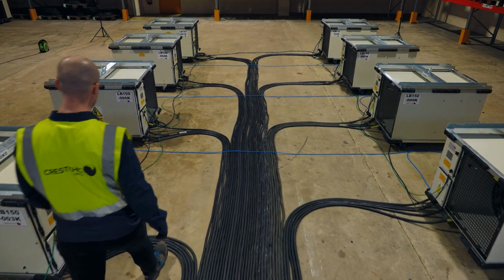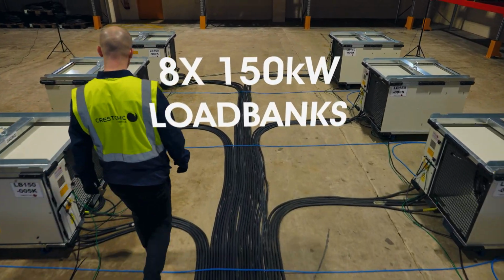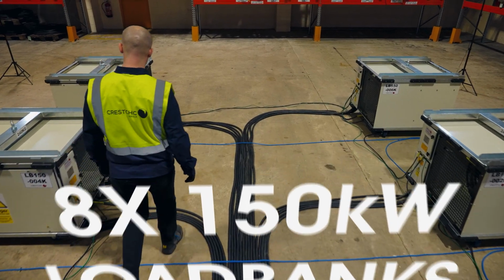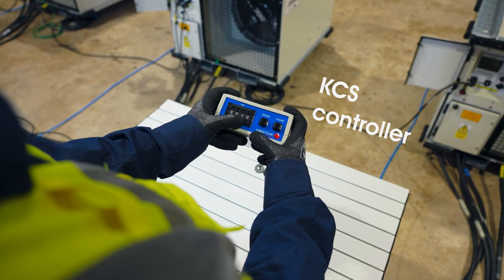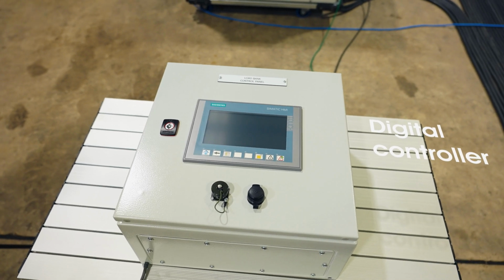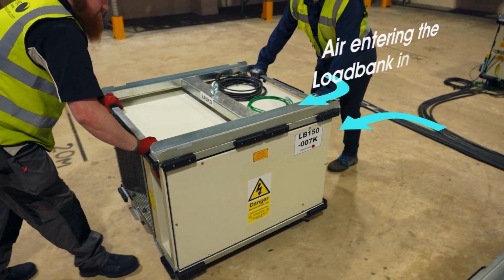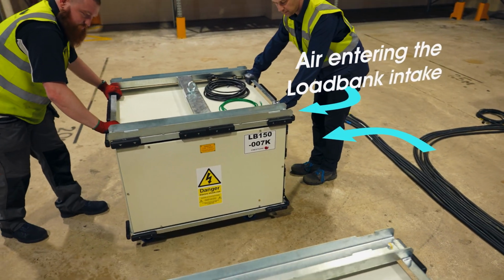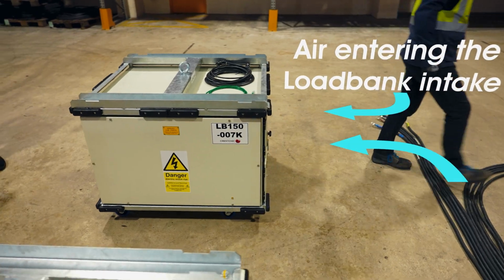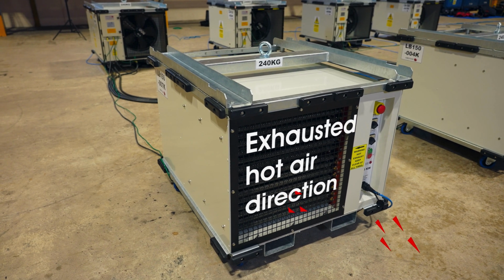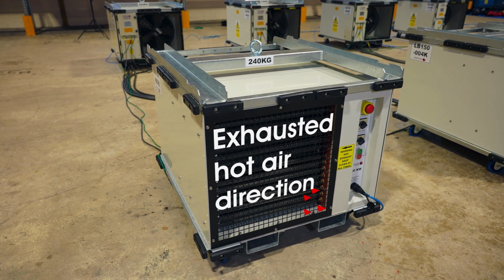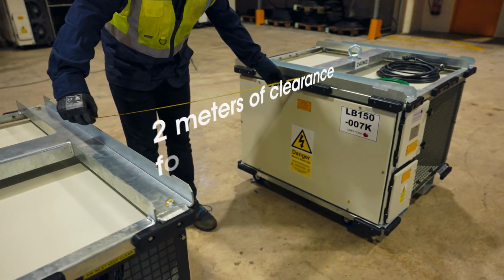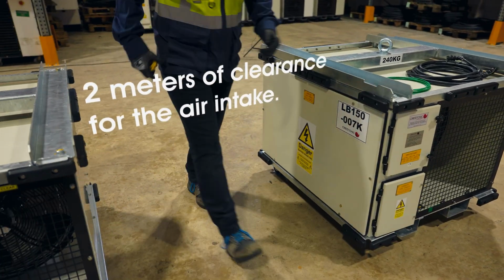In this short video, we are going to show you a typical test using 8 times 150 kilowatt load banks with both our KCS controller and our digital controller. The load bank should be placed so that there is adequate air entering the load bank's intake and the exhausted hot air going away from any other load banks and equipment. We recommend at least 2 meters of clearance for the air intake.